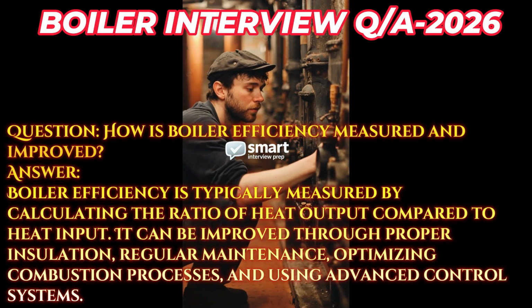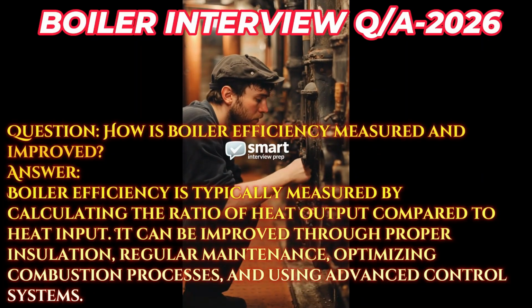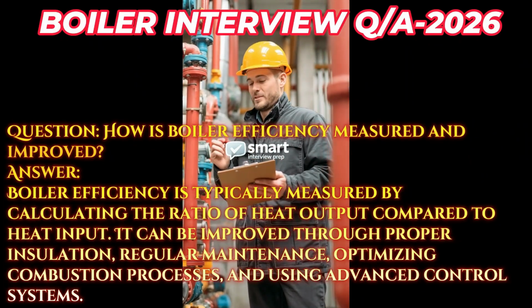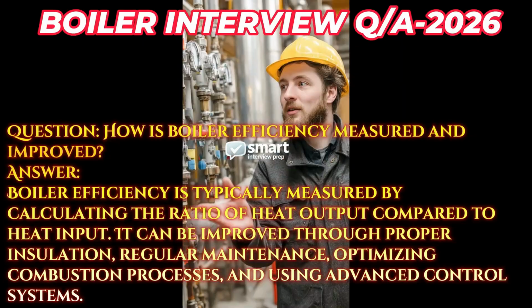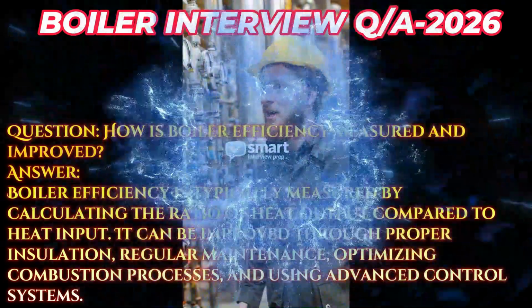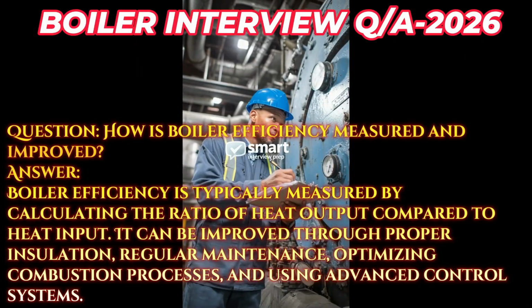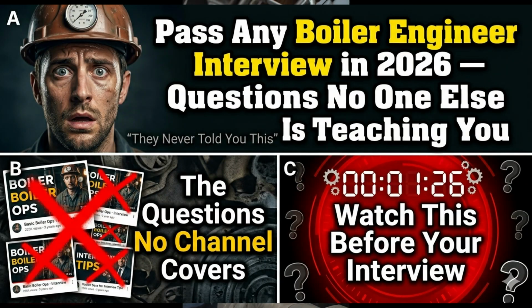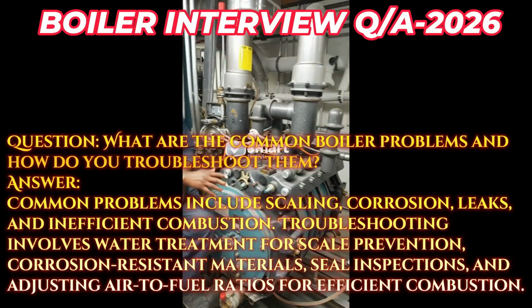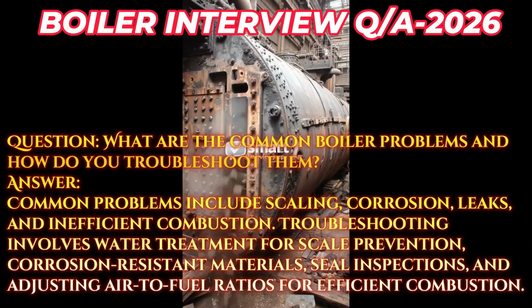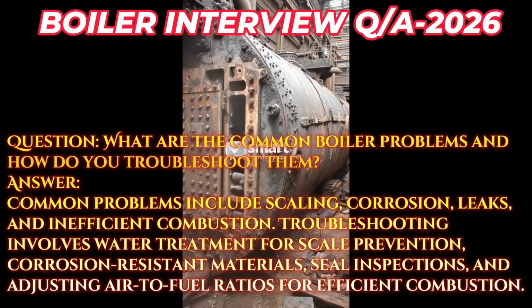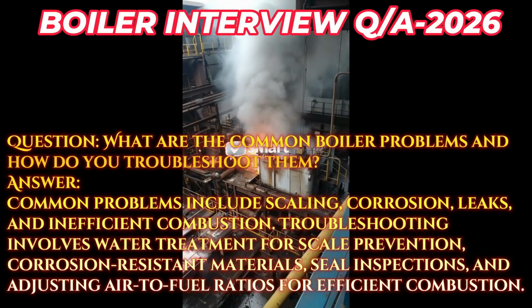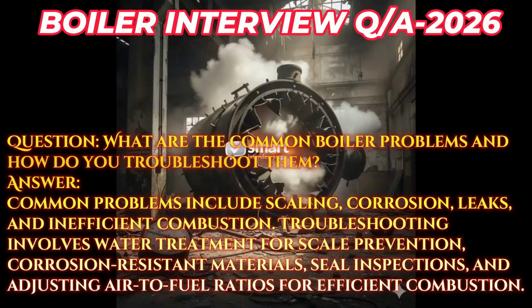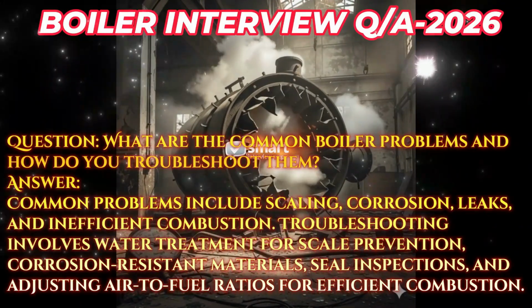Question: how is boiler efficiency measured and improved? Answer: boiler efficiency is typically measured by calculating the ratio of heat output compared to heat input. It can be improved through proper insulation, regular maintenance, optimizing combustion processes, and using advanced control systems. Question: what are the common boiler problems and how do you troubleshoot them? Answer: common problems include scaling, corrosion, leaks, and inefficient combustion. Troubleshooting involves water treatment for scale prevention, corrosion-resistant materials, seal inspections, and adjusting air-to-fuel ratios for efficient combustion.